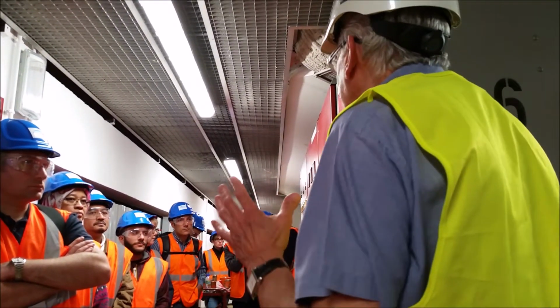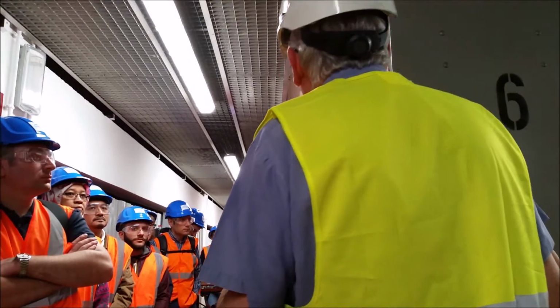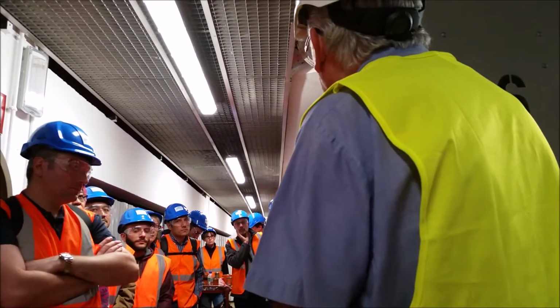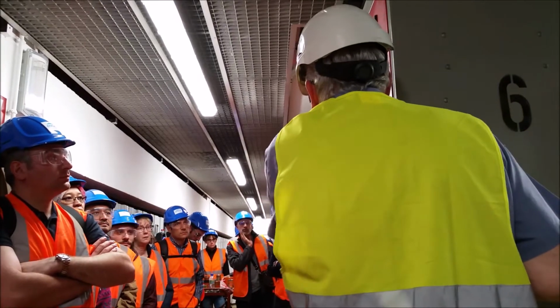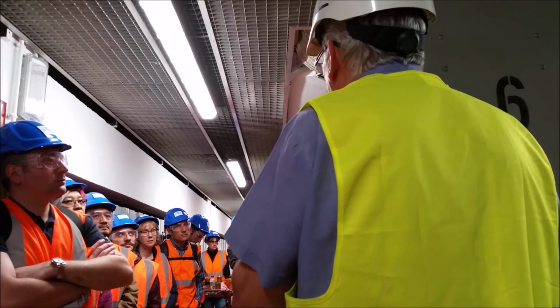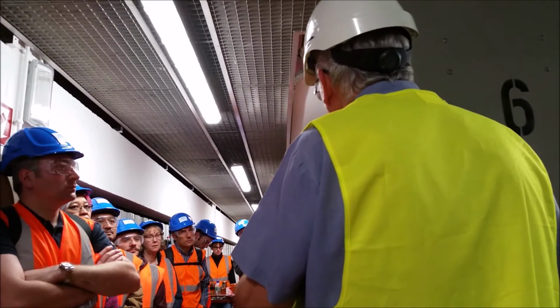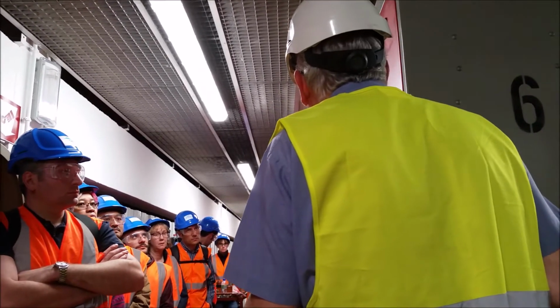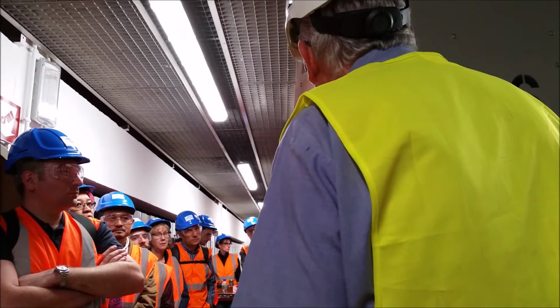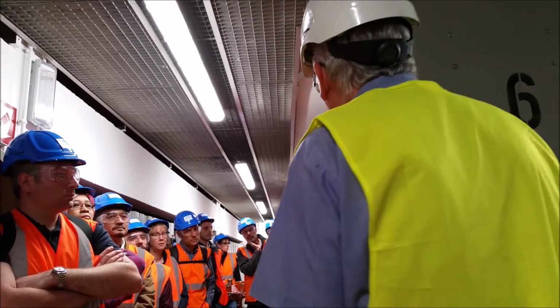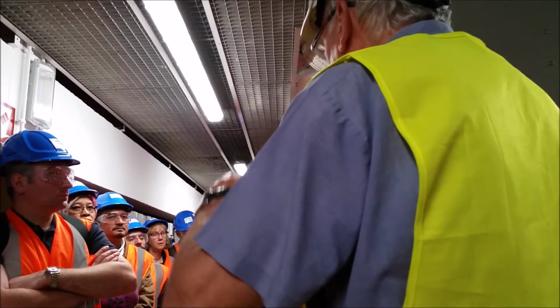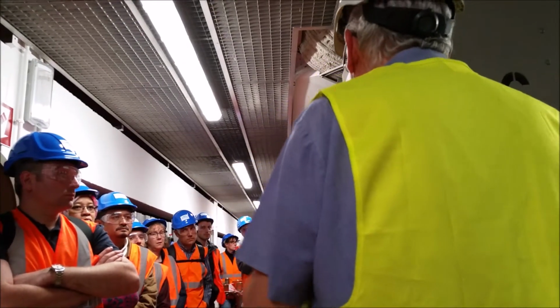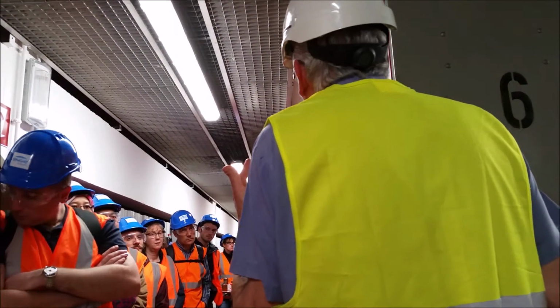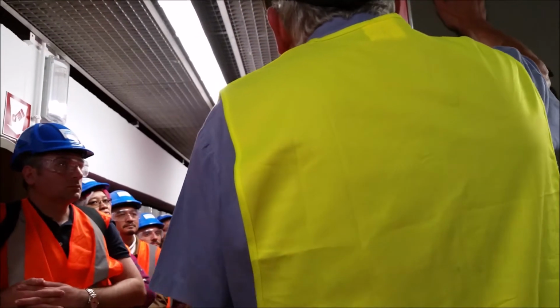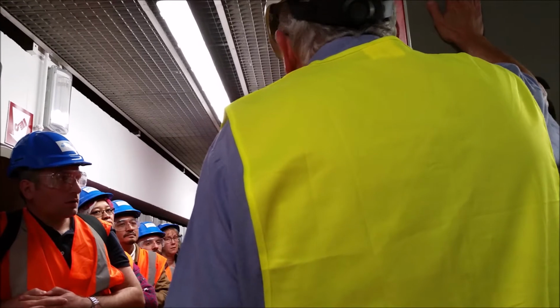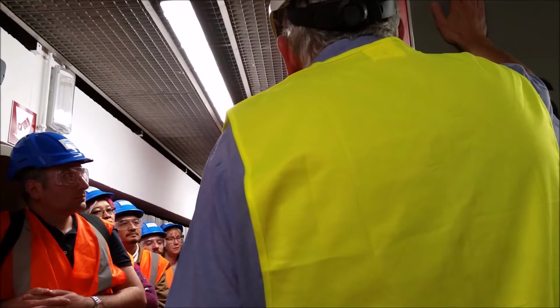The three conditions to switch onto the grid are these. We have to produce from the generator the same frequency. We also have to produce the same voltage as on the grid, 20,000 volt with the step-up transformer to 380 kV, because on the high voltage lines we have 380 kV. And the third condition is the phasing. Our phasing has to be in the same phases as on the grid. When these three most important conditions are completed, we automatically close the circuit breaker, and we can produce.